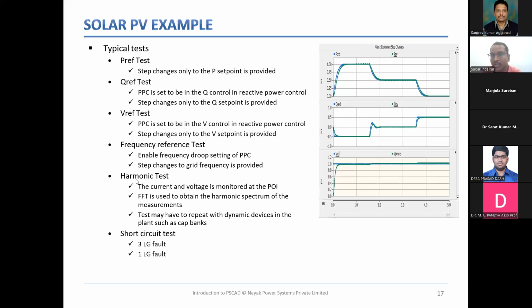Then there is one more test called a harmonic test. So as you know, renewable energy, these are power electronic based devices: solar, wind, BESS, all are power electronic based devices. So they generate harmonics, right? They always have certain harmonic components in them. And as the renewable penetration increases, the harmonics will also increase. So the plant has to take care that the harmonics injected by the plant are within the limits specified by Indian Grid Code. Okay. So typically, the limits which we use are specified in the IEEE 519 standard.